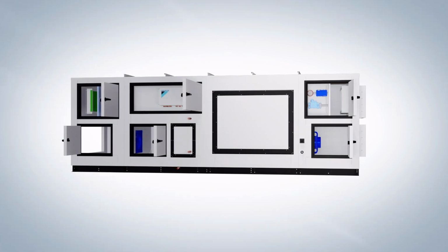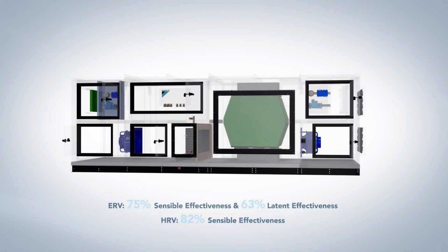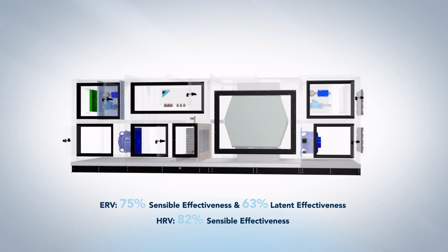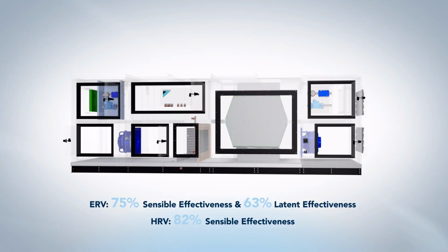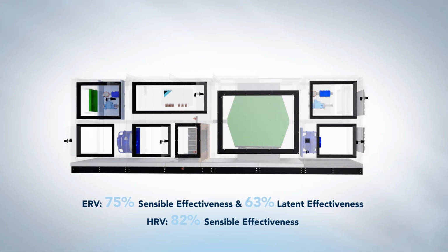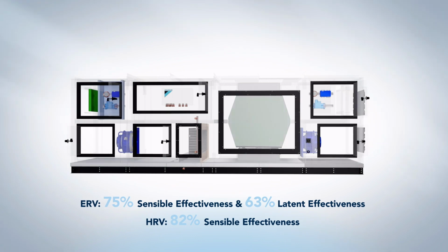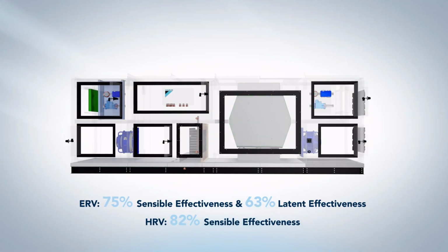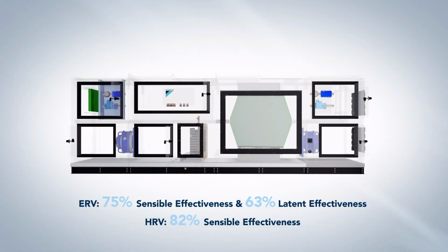outdoor application. The stacked counterflow core allows for high-efficiency sensible and latent recovery, which helps to maintain 30 to 60% relative humidity year-round, has no virus crossover, and makes maintenance easy with no moving parts. An optional integrated bypass section is available for free cooling.